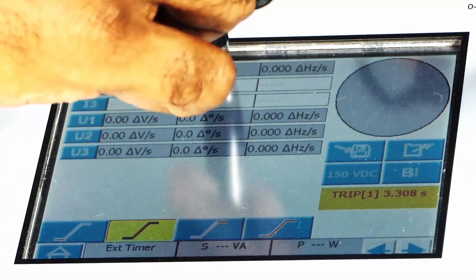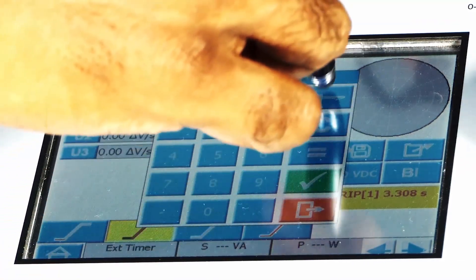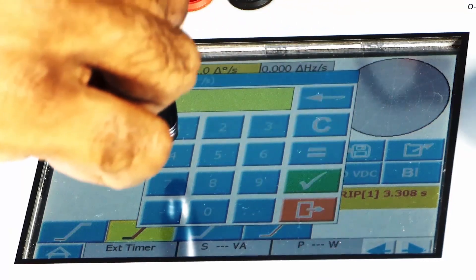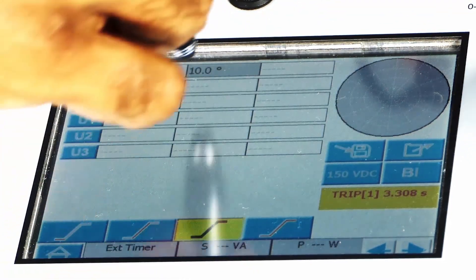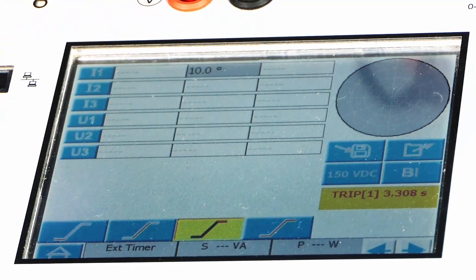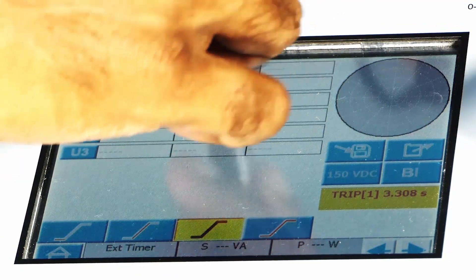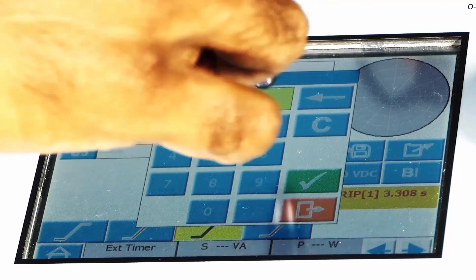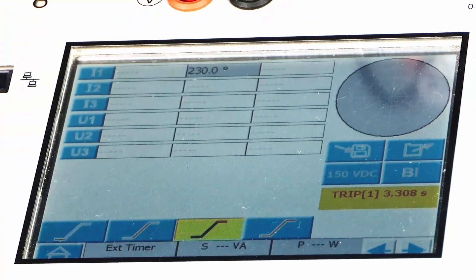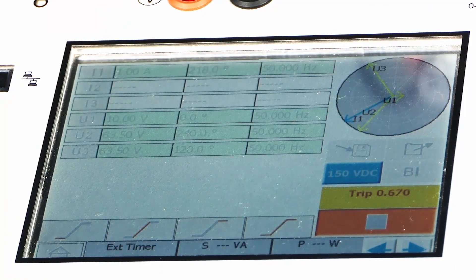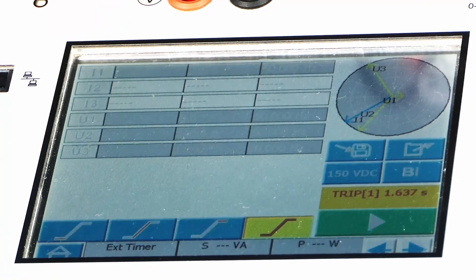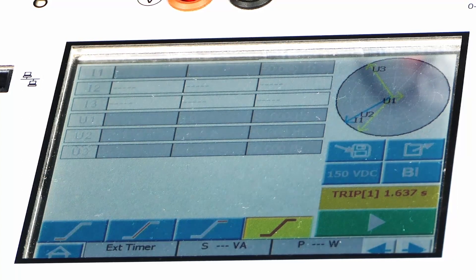The phase angle is incremented in steps of 1 degree, moving up to 230 degrees. By pressing the fourth tab, we can run the test. I am expecting operation near 220 degrees. The results show operation at 219.6 degrees.